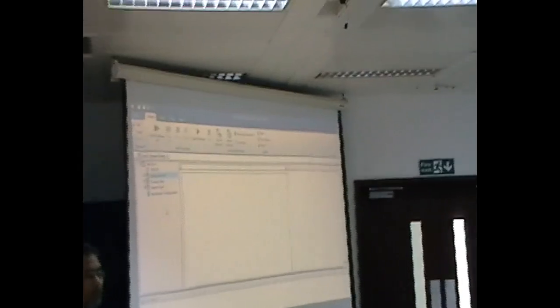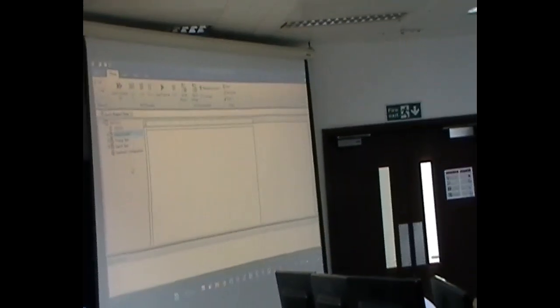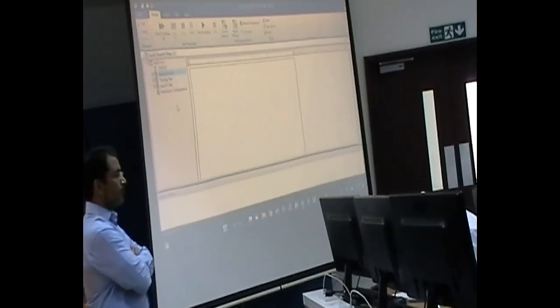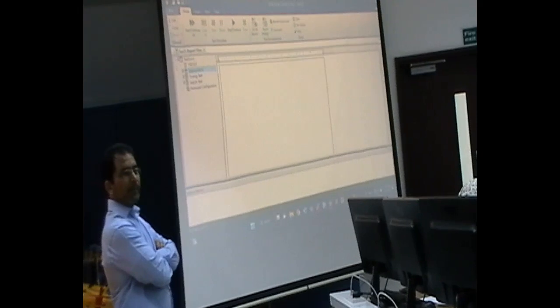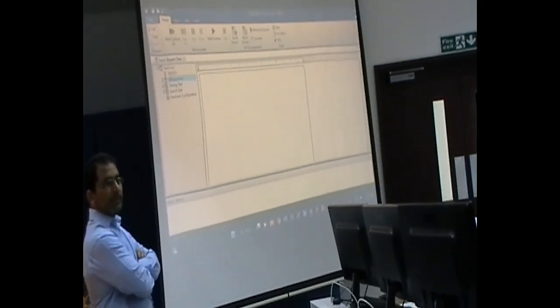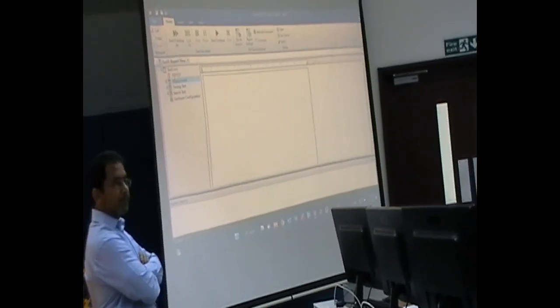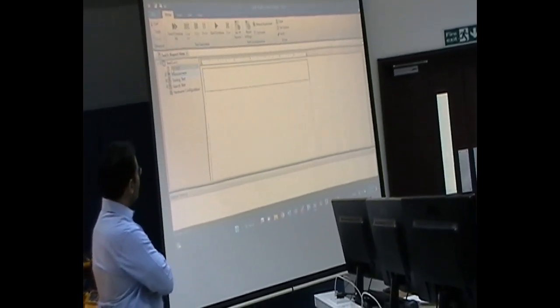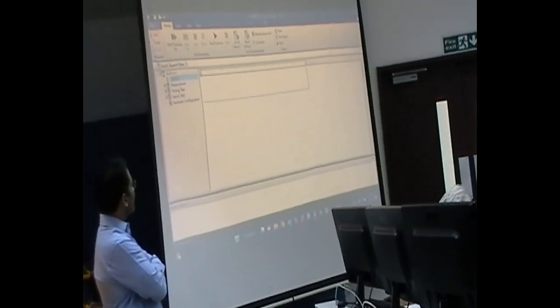Usually, what happens in old days, we will just inject certain value as per whatever we think it's right for the relay, because all test kits will not have such a software. Now the new software, which is Omicron, has the ability to import the setting from the relay and upload it to the test kit. So whatever setting we saw there, we could see it here again in the Omicron software, which is nothing to do with the relay anymore.